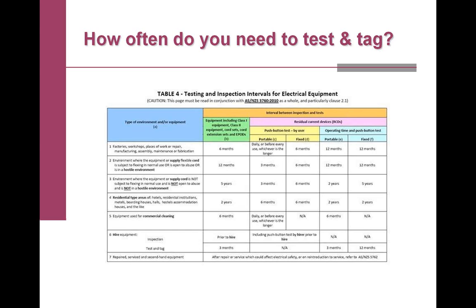Our recommendation is to try not to stray too far from what's within this standard, because of the ramifications. If you said, 'oh no, it's an office environment, let's test it every 5 years,' and something did happen, and it turned out the environment was actually more hostile than an office type, you'd leave yourself a little exposed.